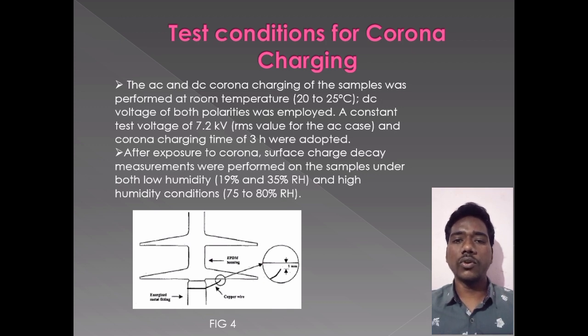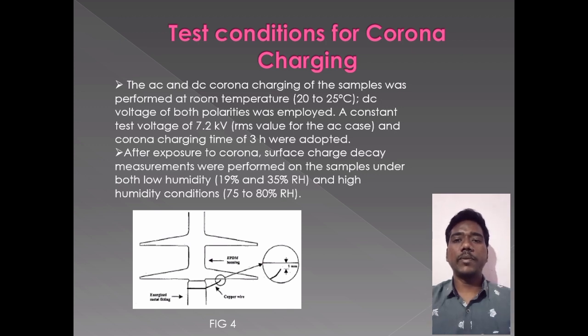After exposure to corona, surface charge decay measurements were performed on the samples under both low humidity and high humidity conditions. The measuring process continued until no appreciable charge magnitudes were detected. Correlation with expected field corona conditions. As an initial approach to comparative estimation of the degree of influence of corona-related processes on insulators operating under actual service conditions, an additional test setup was arranged.